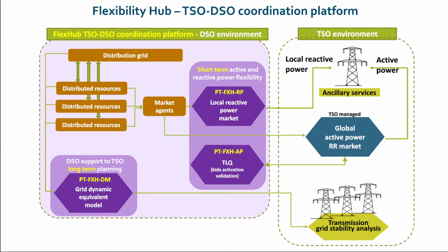For short-term coordination, we have developed a local reactive power market that supplies reactive power to the DSO to balance its own grid, but also supplies reactive power to the TSO at the TSO-DSO connection point for the TSO's reactive power needs.